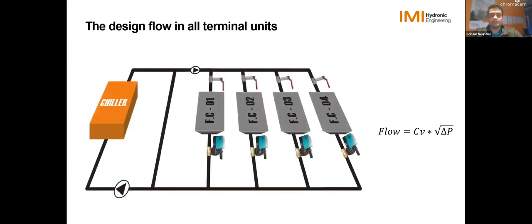So this is the formula for how we calculate the flow on a given balancing valve. So CV is basically the opening that you have on your valve. Your delta P, the differential pressure, is the pressure that you measure through the PT ports. And since we know whatever CV we're picking for the manual balancing device and the delta P that we can measure, we're able to calculate the flow. So let's take an example here today.